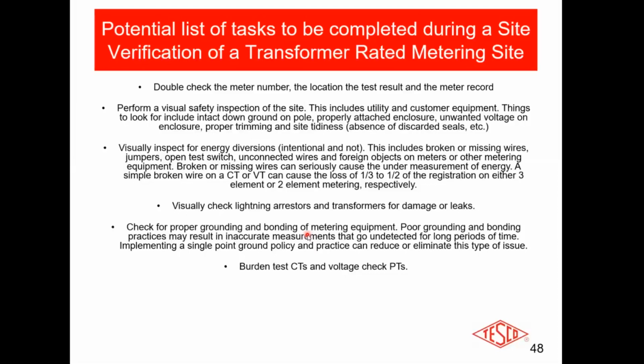You're checking for energy diversion, intentional or not, broken or missing wires, jumpers, open test switches. Nothing more embarrassing than leaving an open test switch. Those plastic covers that fit on the test switch, most people don't use them anymore because they say, the test switch is inside an enclosure, I don't need it for protection. Those covers were actually designed so that you cannot leave an open test switch.